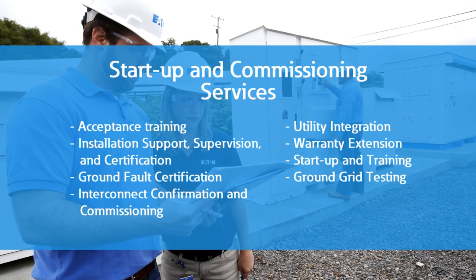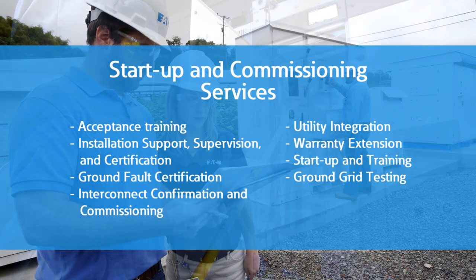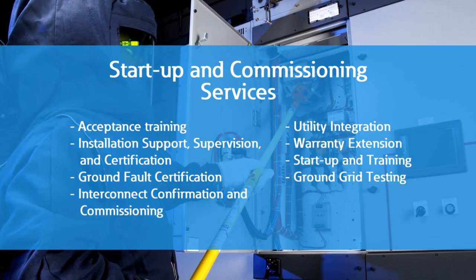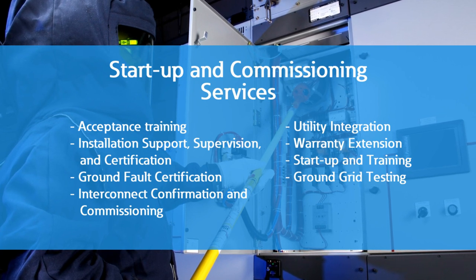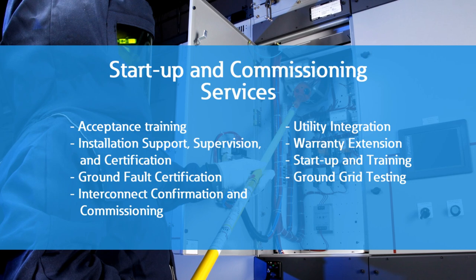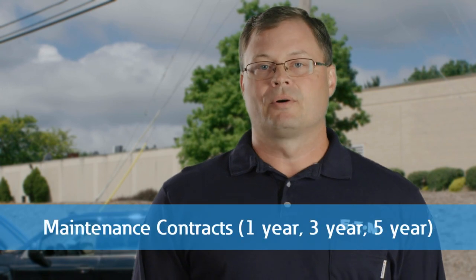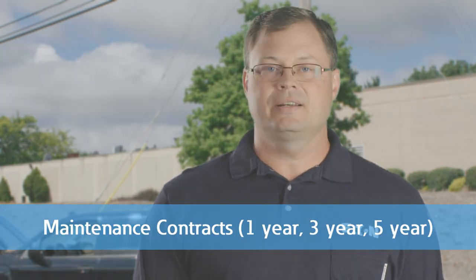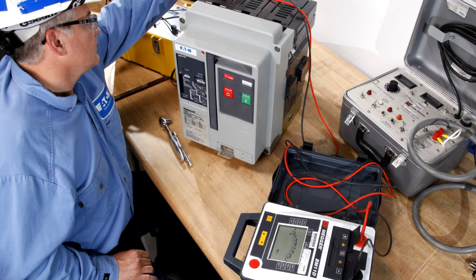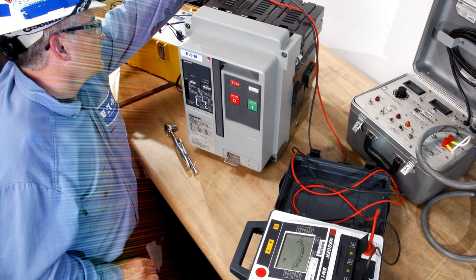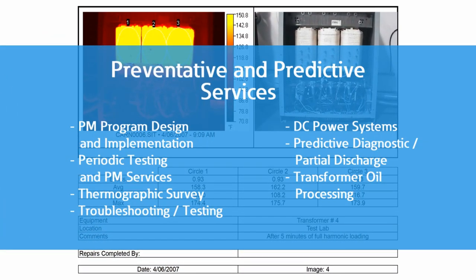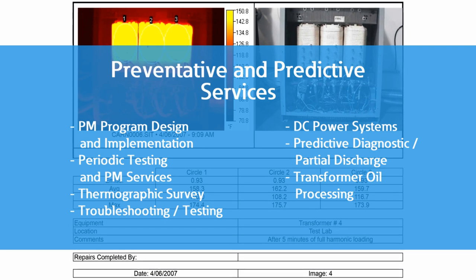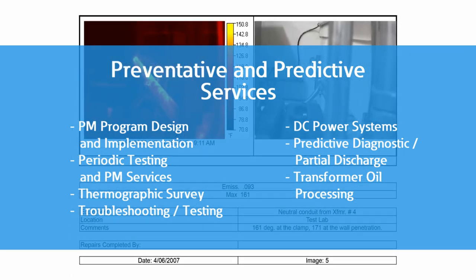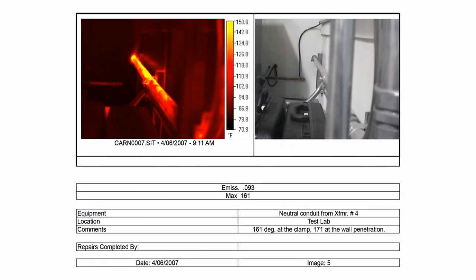It starts at installation. Services surrounding startup and commissioning improve safety, life extension of your equipment, as well as extend your warranty. We also offer testing, including acceptance testing, interconnect confirmation, ground grid testing to further ensure successful installation and environment for your equipment. After installation, maintenance contracts, which may range from annually or even every 3 to 5 years, allow us a routine opportunity to properly assess the condition of your electrical equipment and identify issues before they are failures. Predictive diagnostics, including partial discharge, thermographic surveying, transformer oil processing, are only the start of the services we can provide post-install to test the reliability of your power system.